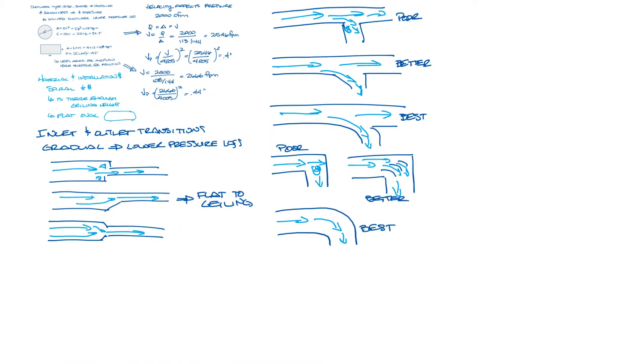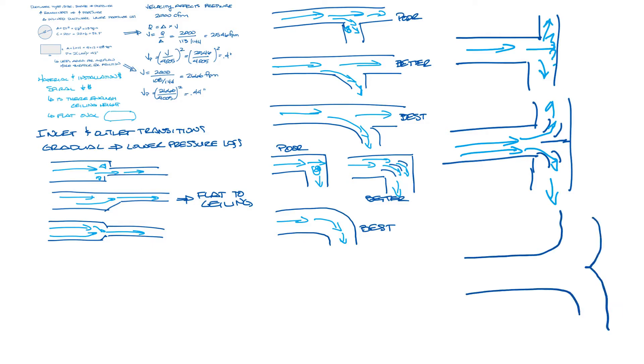Let's look at T's. Much like 90 degree bends and T off, you'll have a lot of turbulence here where the air is hitting this back side. If you could put in turning vanes, now this will help your air flow, turn the corner and reduce your pressure loss. And then ideally, you would have two soft 90s going in opposite directions for the lowest pressure loss.